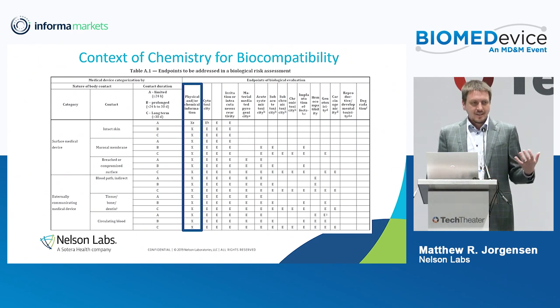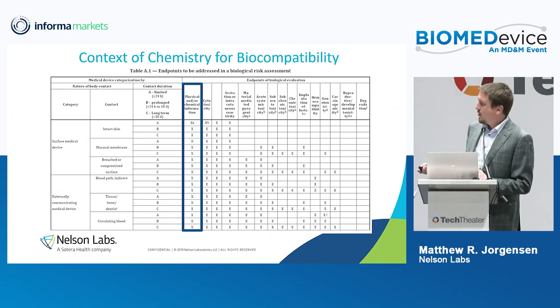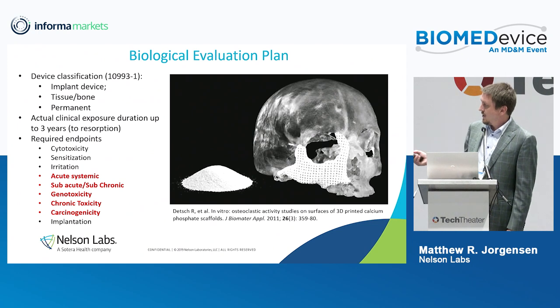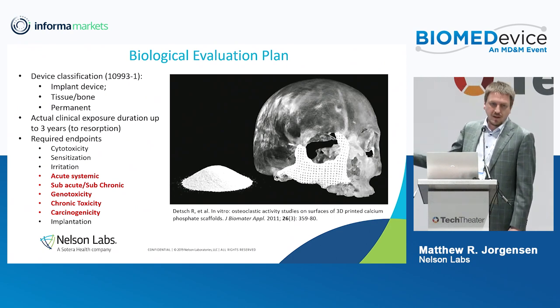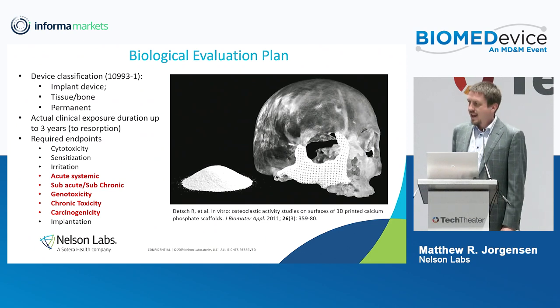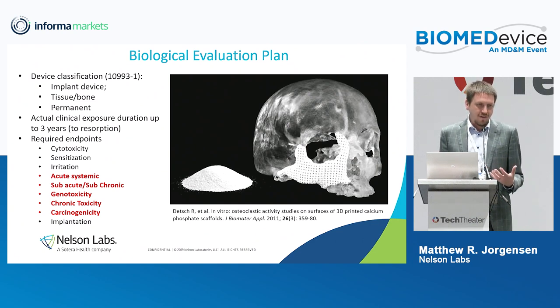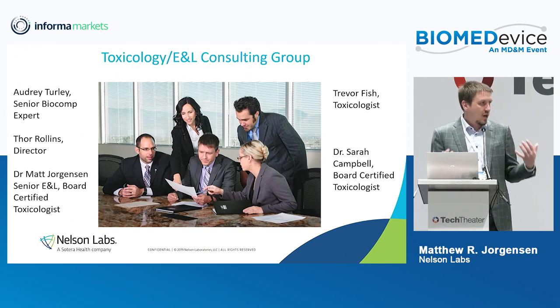The suggestion is that no matter what type of device you have, you should take a step back and ask yourself: what am I making my device out of? Is this safe? Does it not only meet physical performance requirements, but is it a biocompatible material? For example, if you have a device that's some sort of permanent implant, you would categorize that as permanent tissue bone contacting. According to 10993-1, that full list of biological endpoints would need to be evaluated.